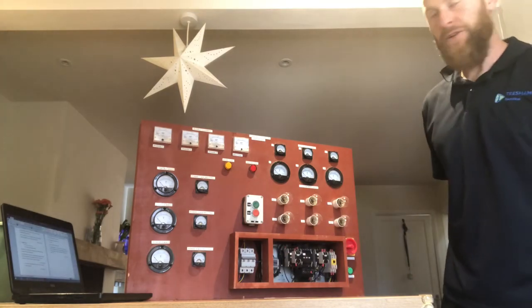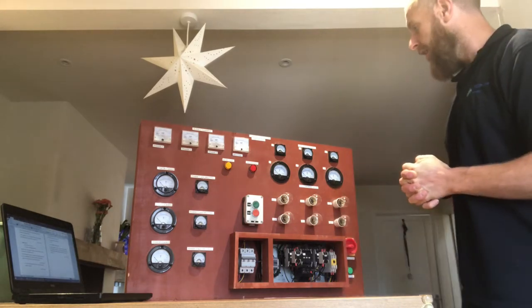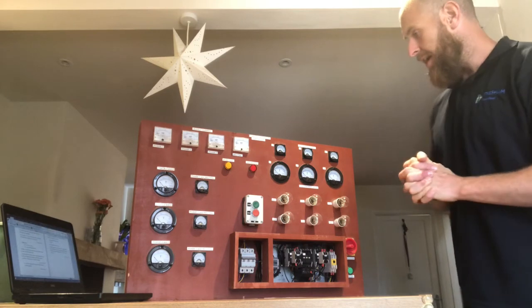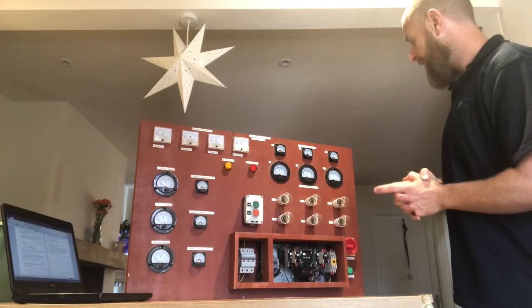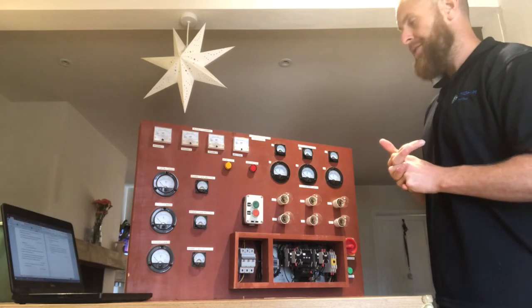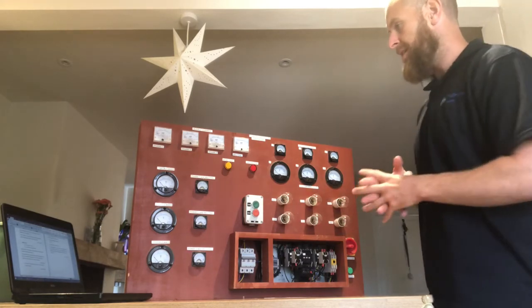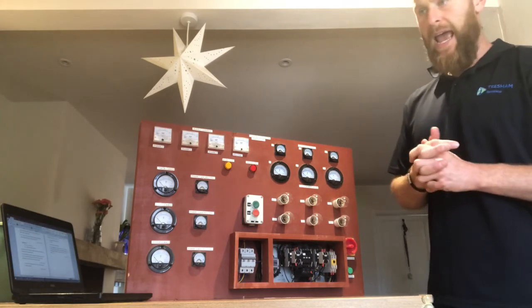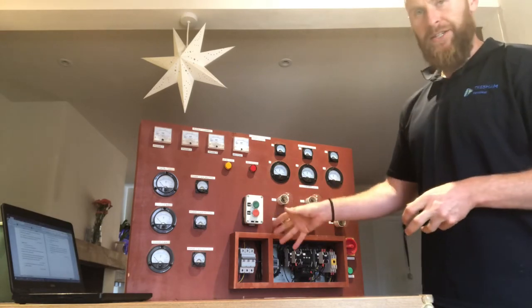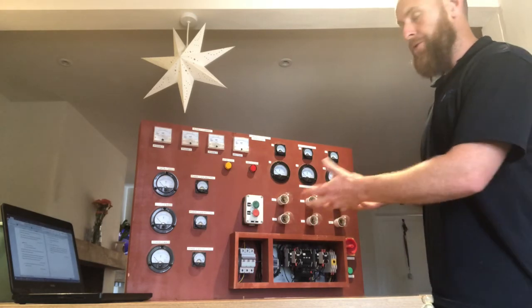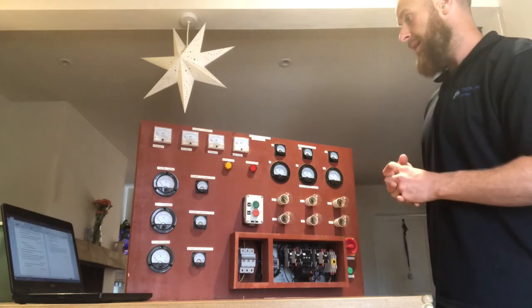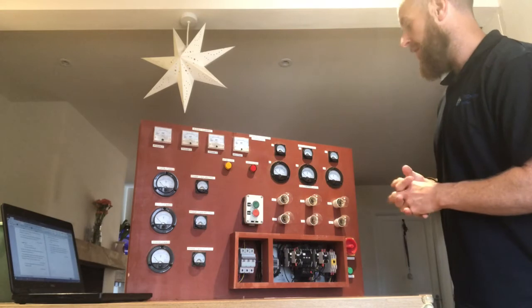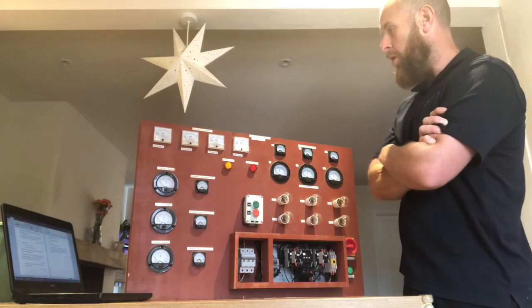The other question to do with the prevention of electric shock was use of RCDs. Now there is no RCD on this, there is a circuit breaker but there is no RCD. That comes under regulation 415 and it should have had, I would have liked to have put a built-in RCD on this, but all of the college where we are going to be using this everything is RCD protected, so I didn't want to actually build an RCD into this because that could cause problems with the other RCDs tripping. So at the moment this is completely non-RCD protected but it's okay when it's plugged in.